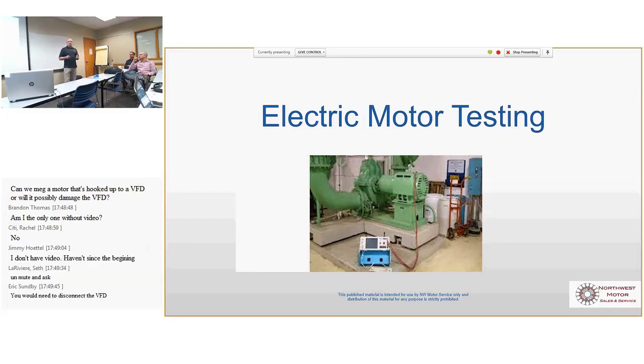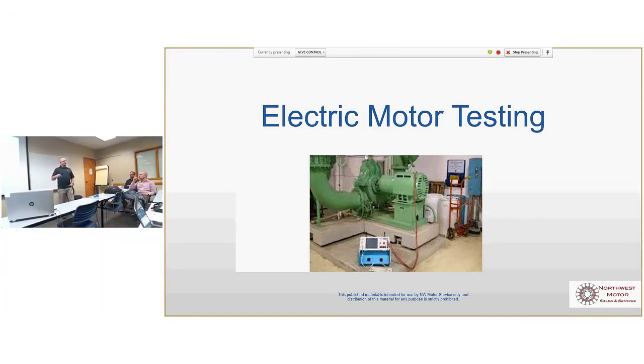And the test is called dynamic testing, and this is called static testing or offline testing. The live test is what we call dynamic, and it is like a full systems test. So I'm hooking up to all 3 phases and monitoring the voltage and current on all 3 while the motor's running and checking for harmonics, under, over voltage, current imbalances, using the motor as a sensor and checking the load, so the fan or the motor, and seeing if there's any kind of weird mechanical problems. So it's a good test, but it's not testing the insulation like this is.